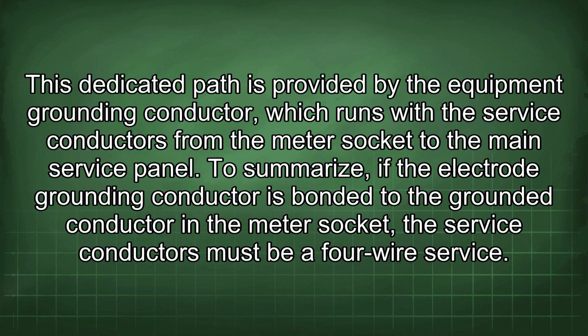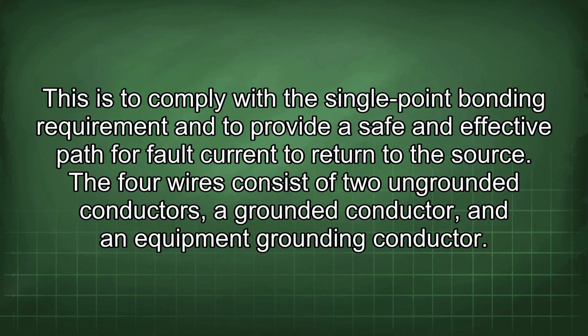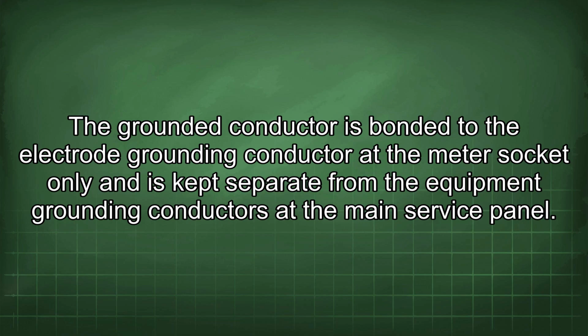To summarize, if the electrode grounding conductor is bonded to the grounded conductor in the meter socket, the service conductors must be a 4-wire service. This is to comply with the single-point bonding requirement and to provide a safe and effective path for fault current to return to the source. The 4 wires consist of 2 ungrounded conductors, a grounded conductor, and an equipment grounding conductor. The grounded conductor is bonded to the electrode grounding conductor at the meter socket only and is kept separate from the equipment grounding conductors at the main service panel.